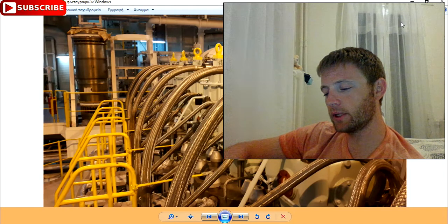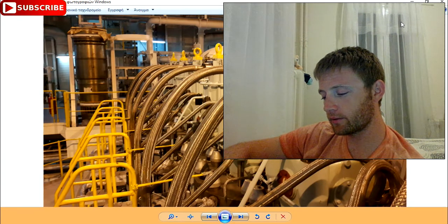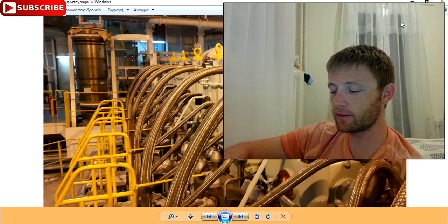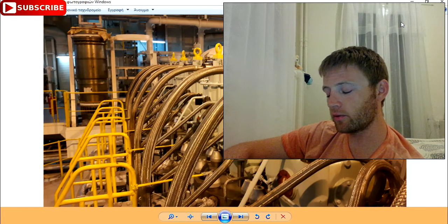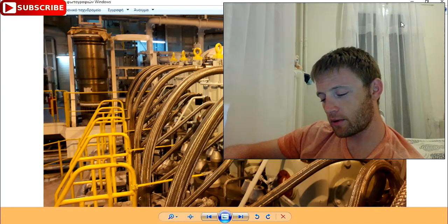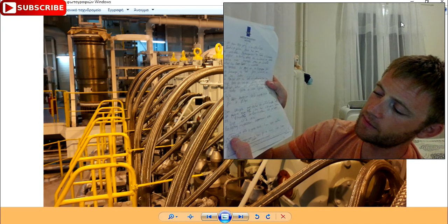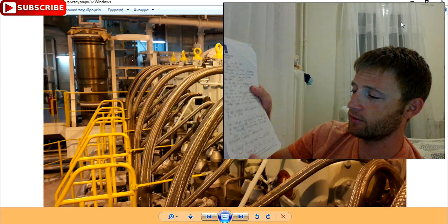48, the beta plays a big role for the filter, okay? Beta. 49, when we have one pump working, we change the oil in this pump. Inside there remains 10%, and we say to the company that we have 10% contamination, and we ask them if it's good, okay? Pre-dock inspection is very important, okay? And for the wear ring, with some sign, about 0.3 millimeters is good for the ring. 1 millimeter is too much. Okay.